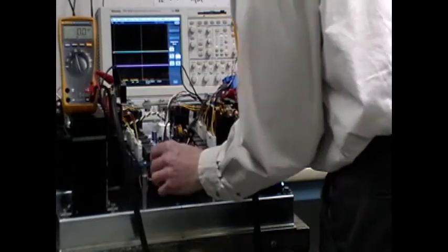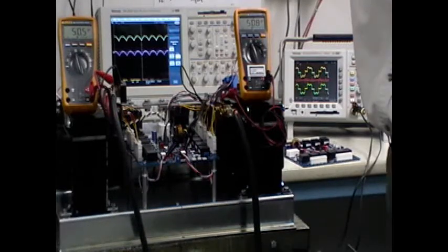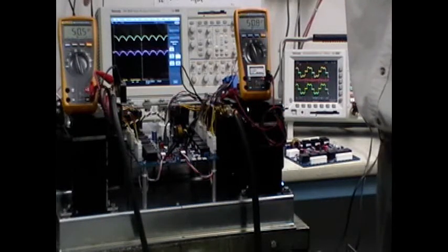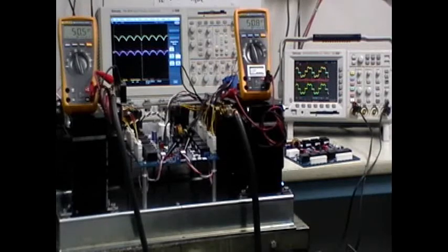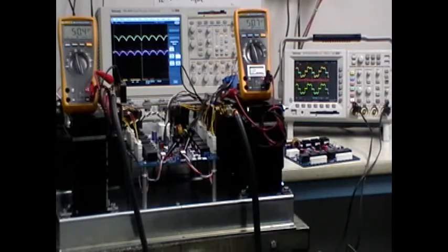I'll install the current feedback and we'll see how well it shares. So again, we go to approximate the same amount of total current, but here we have 50.5 millivolts, which is 101 amps. And here we have 50.8 millivolts, which is 101.3 amps. So there's a 300 milliamp difference out of 200 amps, which is about 0.15 percent accuracy.